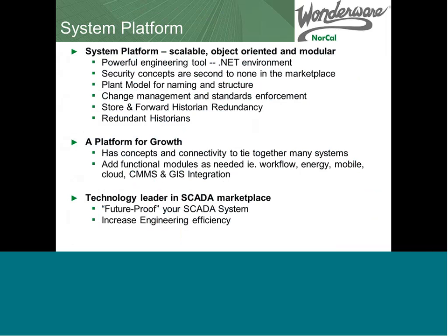So if you've got commonality in pump stations or lift stations, RTUs, you can create standards. You can create a standard template that you use for your RTUs and pump stations, and reuse that template over and over. If you add a new RTU, it makes it very simple to cookie-cutter that out and drive changes through the parent template.